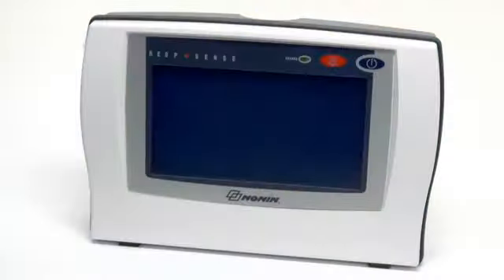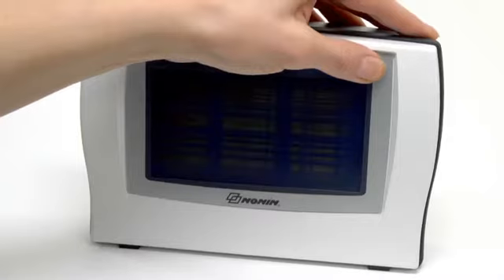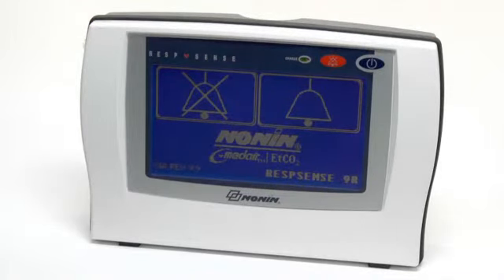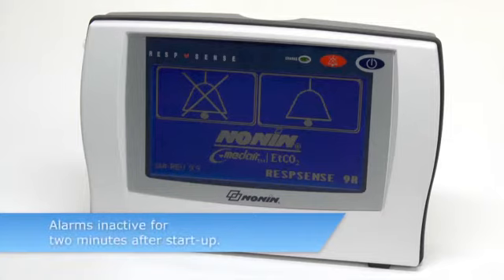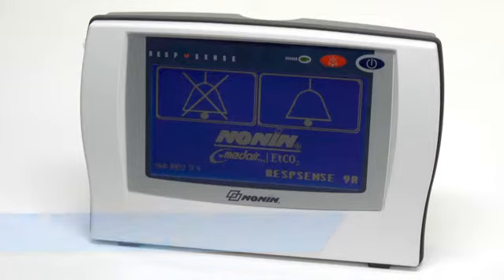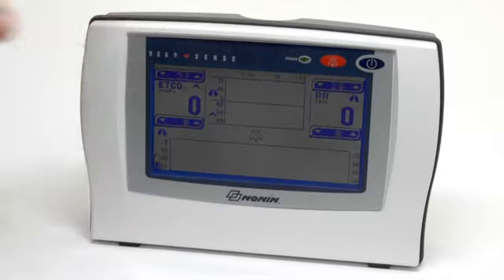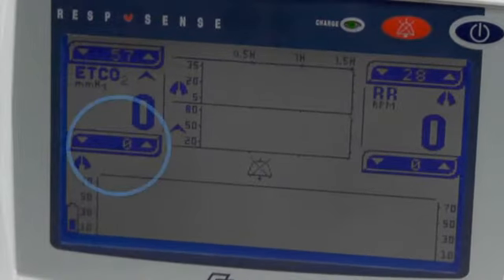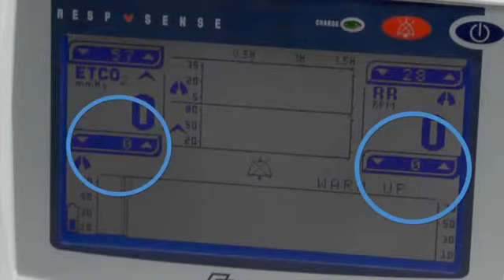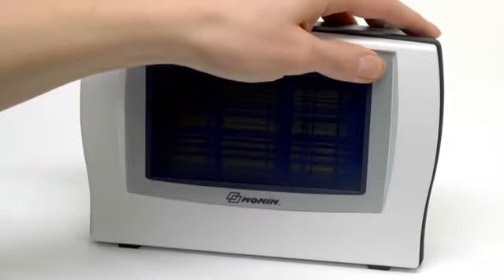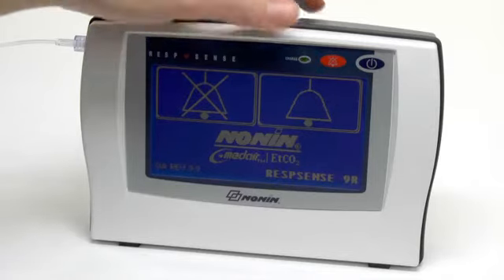Turn on the RespSense monitor by pressing the on-off button in the upper right corner until you hear a beep. The monitor will run a brief self-test. After a few seconds, you will see several entry selection screens to choose initial settings. Alarms remain inactive for 2 minutes after starting the monitor. The first screen allows you to enable or disable alarms. The Disable Alarms icon drops all minimum alarm values to 0. You will then see the main screen. The Enable Alarms icon sets alarms to the default limits.